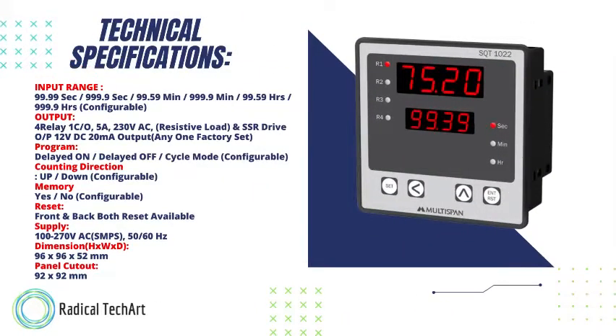Looking at its specifications. Technically, input range is selectable in second, minute, and hours — 99.99 — and you can select a decimal point as per your application. Output is 4 relay. In this you have 3 modes: delay on, delay off, and cycle mode. Counting direction is up or down configurable. Memory is yes or no configurable. Front and back both reset available. Supply voltage is between 100 to 270 volt AC, 50 to 60 hertz frequency. Dimensions of this model is 96 by 96 and the panel cutout is 92 by 92 mm.